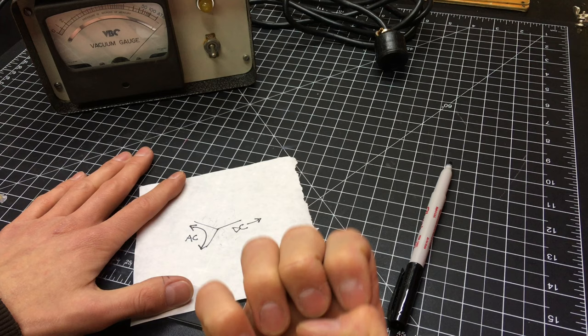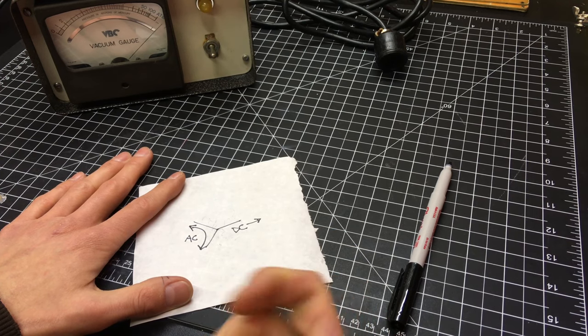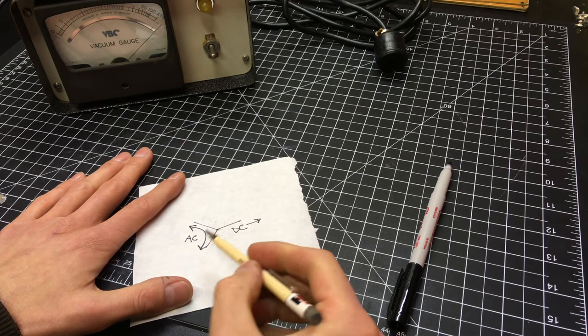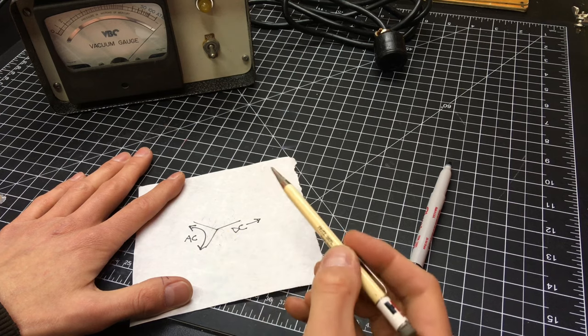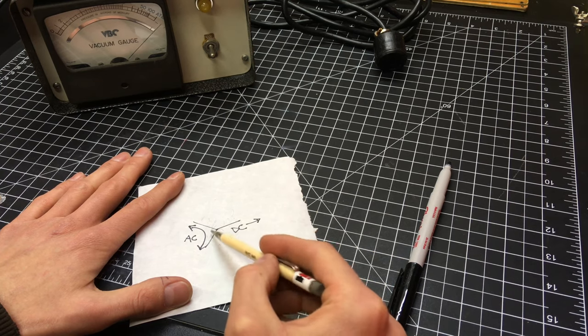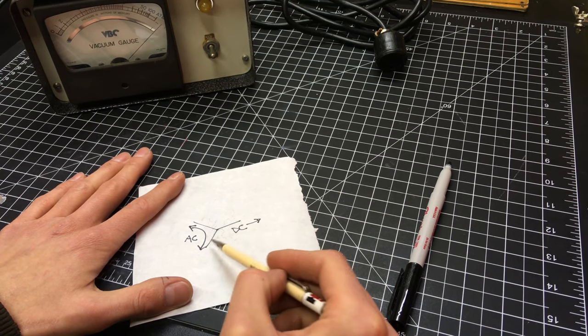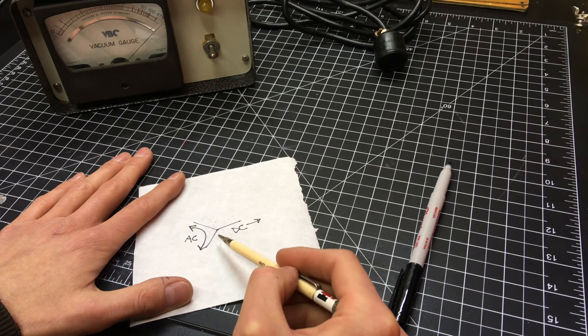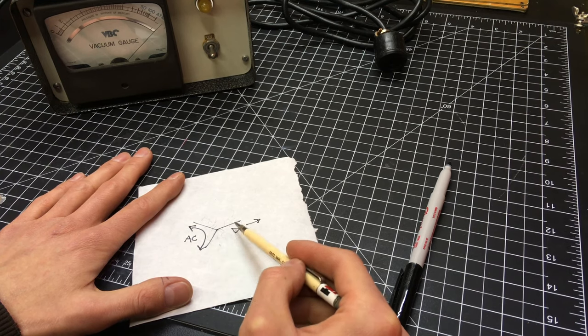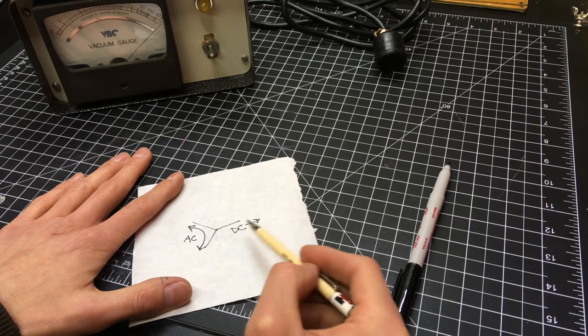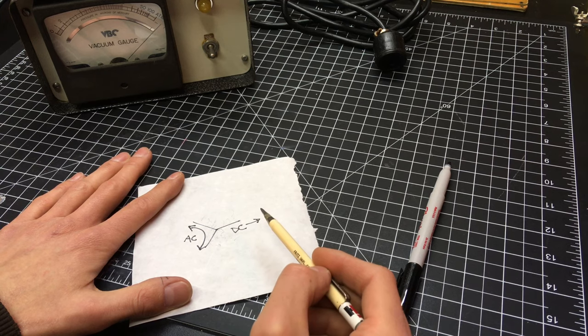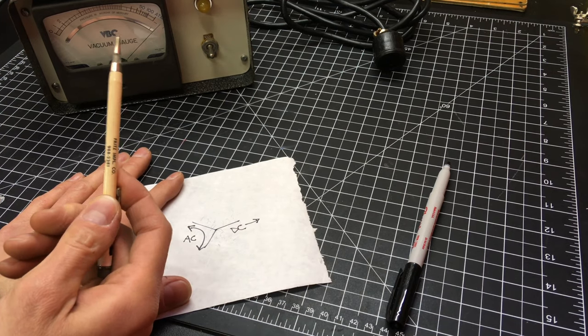As the vacuum system draws the gas molecules out there are fewer and fewer inside the gauge tube and so there are fewer molecules bumping into the wire and the wire gets hotter. As the wire gets hotter it creates more DC current and it moves the needle.